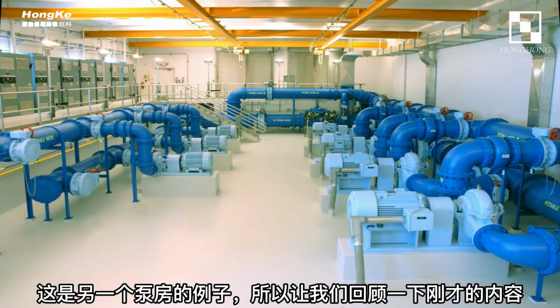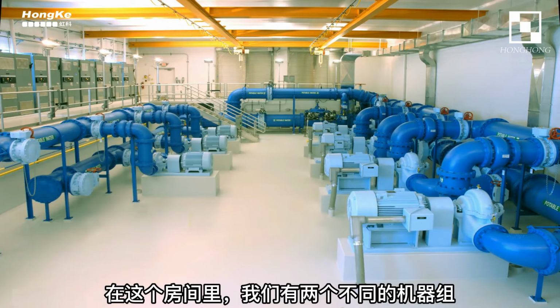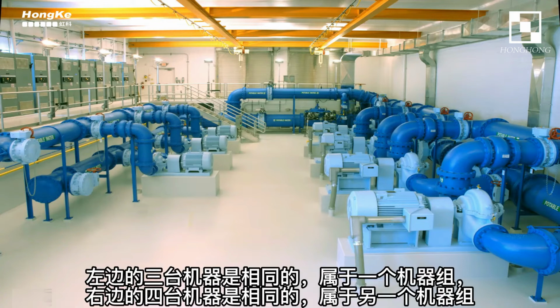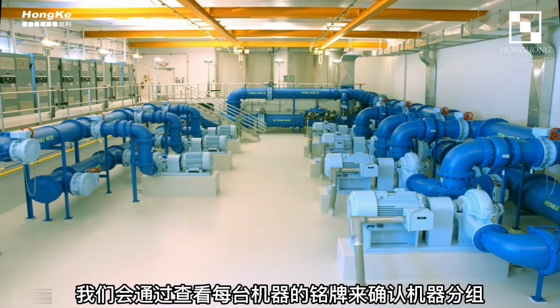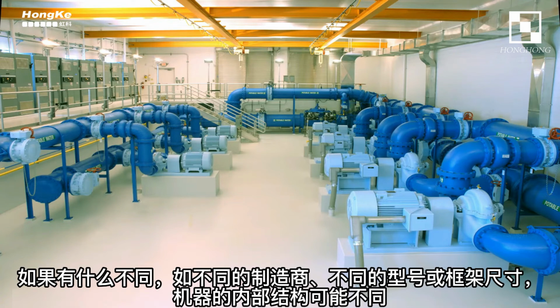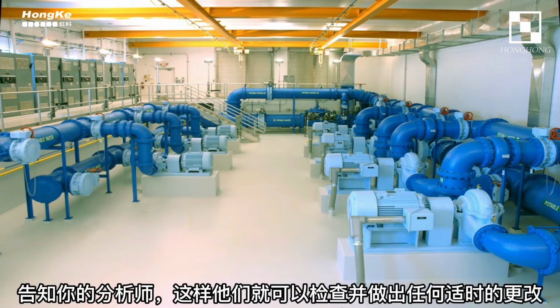Here's another pump room example. So let's review what we covered. In this room, we have two different machine groups. The three machines on the left seem to be all identical and would be one group. And the four machines on the right all seem to be identical and would be in its own group. We would confirm this by looking at the nameplates of each. If there is something different, like different manufacturer, different model, or frame size, the internals of the machine could be different. Let your analysts know so they can review and make any applicable changes.